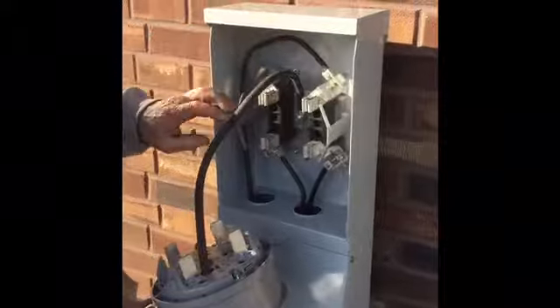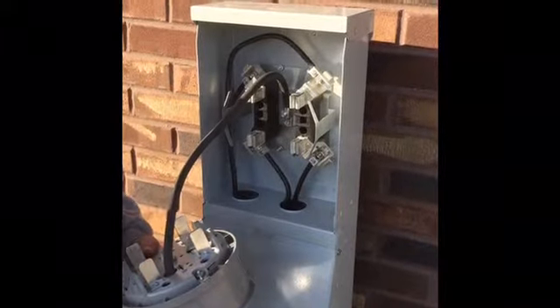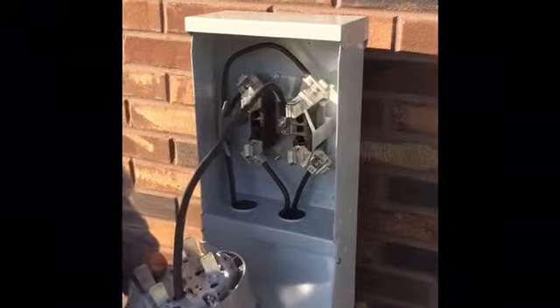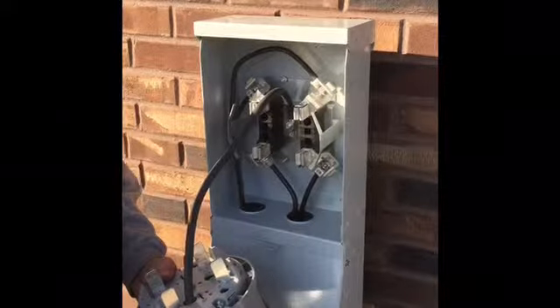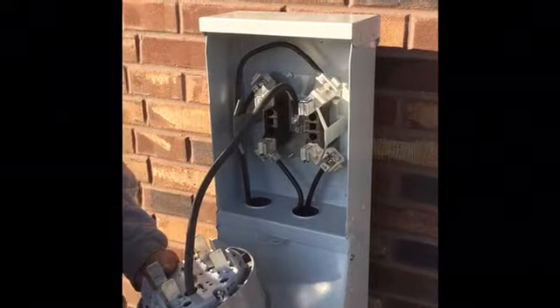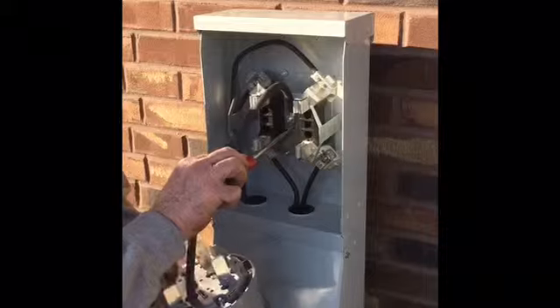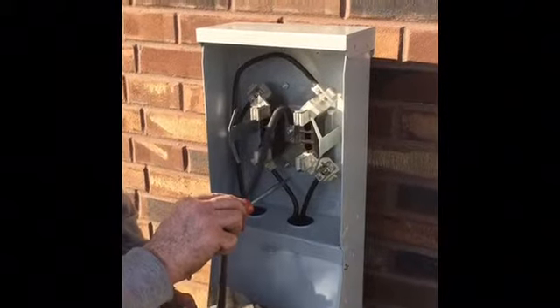Okay, the next step we're going to do here is connect our neutral pigtail to the customer's neutral lug on the meter socket, and this is a critical step. What we're doing here is ensuring that we have a good neutral.